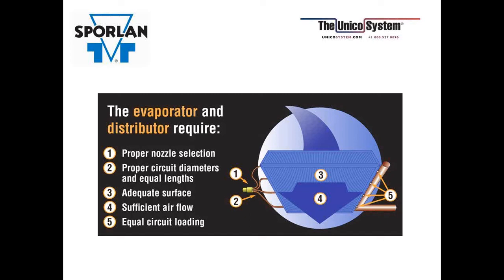If you don't have the proper airflow across the coil, you'll not get the heat exchange needed for the system to run efficiently, and you'll not get the cooling you need. So Pete here will tell you how many CFMs Unico requires. Minimum 200 CFM at all times. And remember, don't try to reinvent the wheel. Craig Messmer spent a lot of time on R&D coming up with the right sizes for everything here. This lack of airflow is one of the biggest issues that Unico sees in their troubleshooting on their tech support. 95% probably.